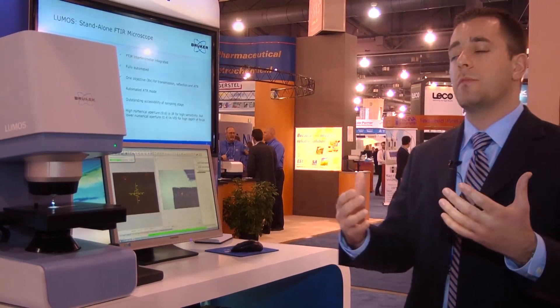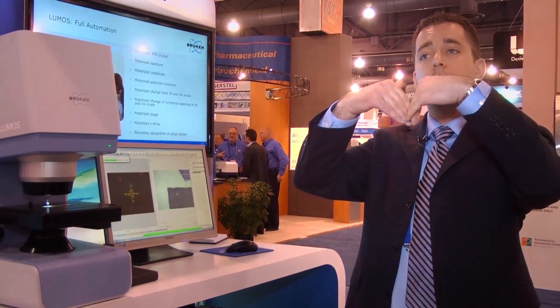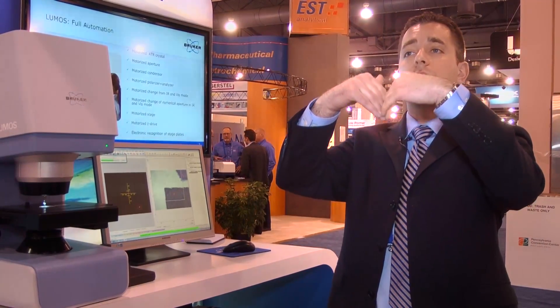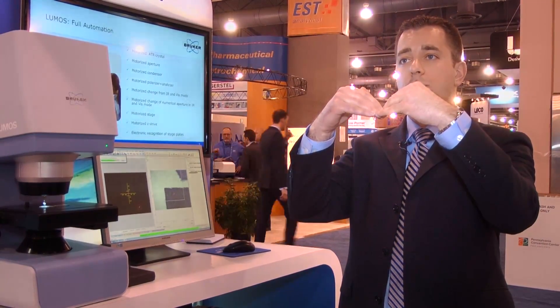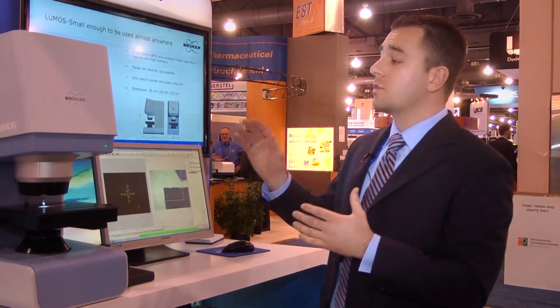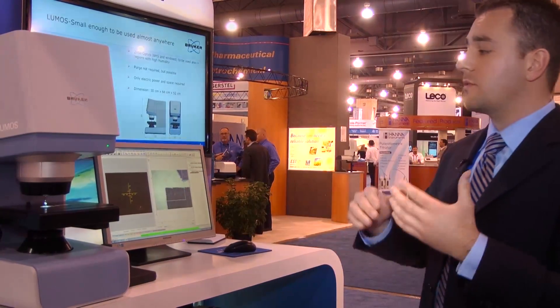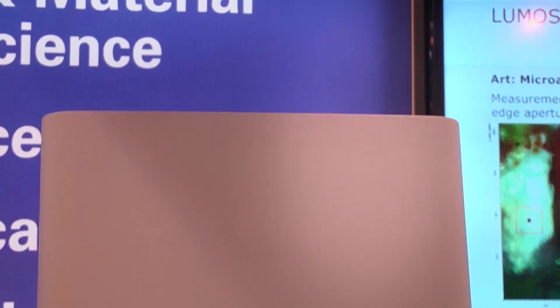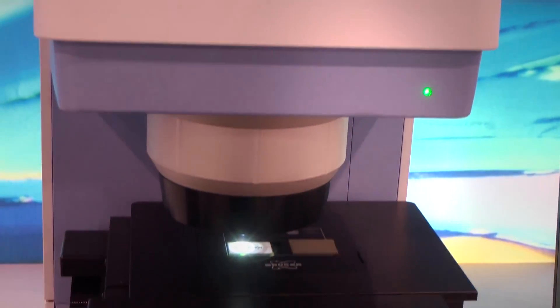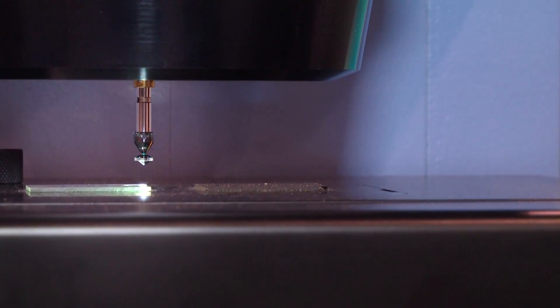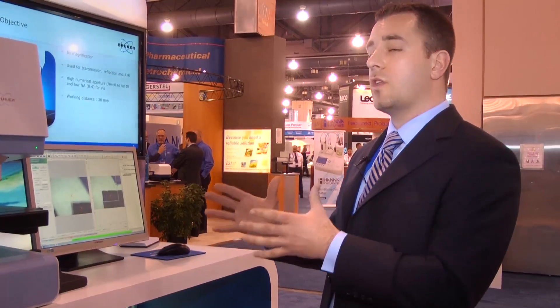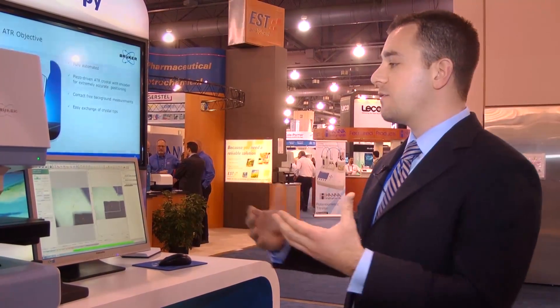In a standard visible microscope, you want a low numerical aperture to get the best visible focus on your sample. But when you take an infrared spectrum, you actually want a higher numerical aperture to collect all of the scatter coming off your sample. In the Lumos, this happens automatically: we collect the visible image under a 0.4 numerical aperture, and when you switch to infrared, it automatically switches to a 0.6 numerical aperture, giving you the best visible clarity and the best infrared data.